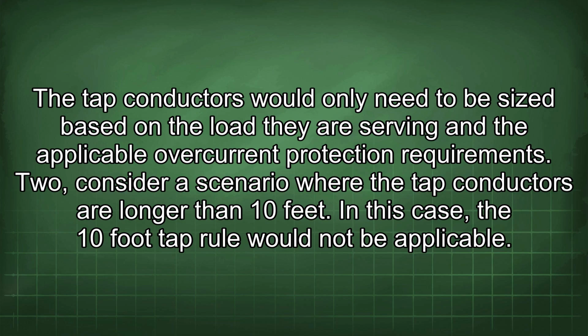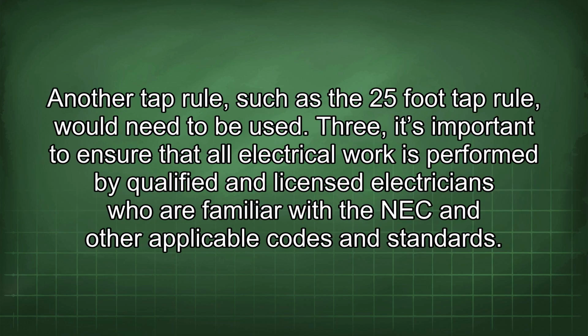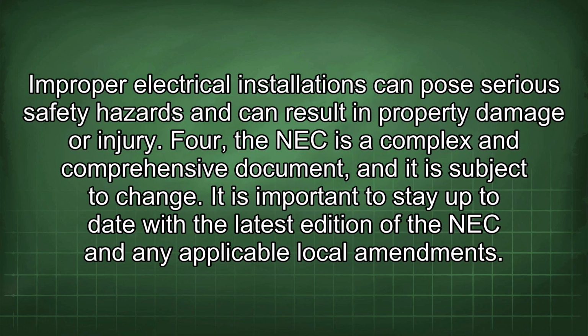2. Consider a scenario where the tap conductors are longer than 10 feet. In this case, the 10-foot tap rule would not be applicable. Another tap rule, such as the 25-foot tap rule, would need to be used. 3. It's important to ensure that all electrical work is performed by qualified and licensed electricians who are familiar with the NEC and other applicable codes and standards. Improper electrical installations can pose serious safety hazards and can result in property damage or injury. 4. The NEC is a complex and comprehensive document, and it is subject to change. It is important to stay up to date with the latest edition of the NEC and any applicable local amendments.